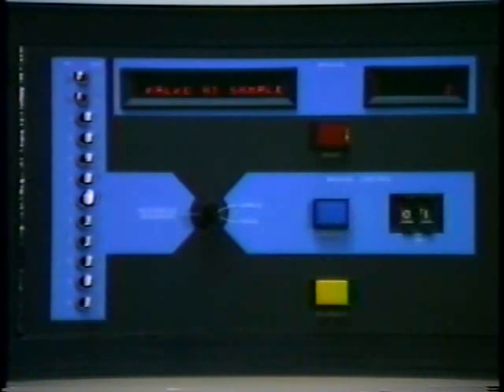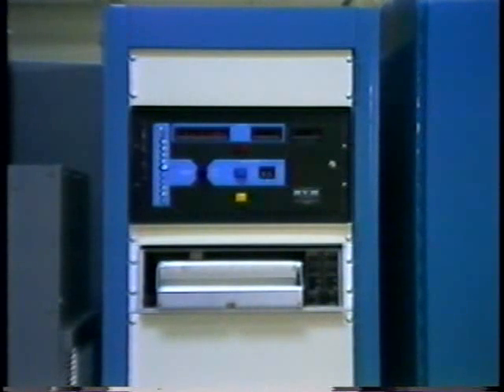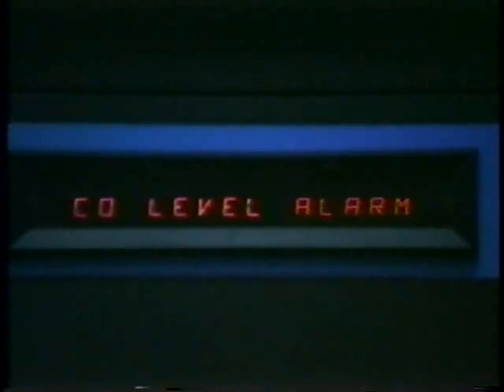The operator may instantaneously gain manual control over the system by use of control switches, and is kept continuously informed of system response to commands by the bright alphanumeric display. Restoration to automatic control is just as simple. The computer's primary function, however, is to relieve the operator of interpretive duties and exposure to false alarms. On first sensing a rising carbon monoxide level, the computer automatically determines the location of the potential fire and verifies proper system operation, including calibration of the analyzer. Only then does the alarm sound.